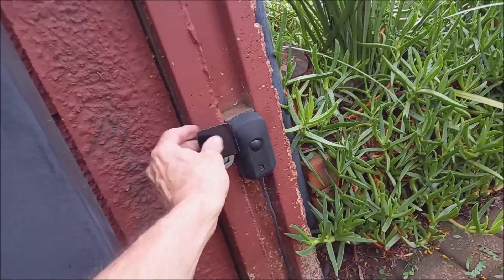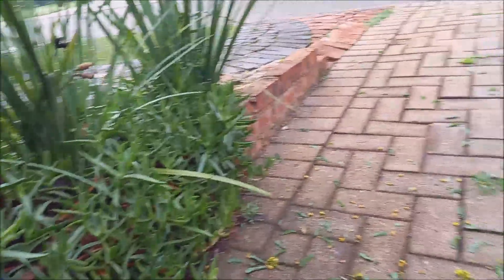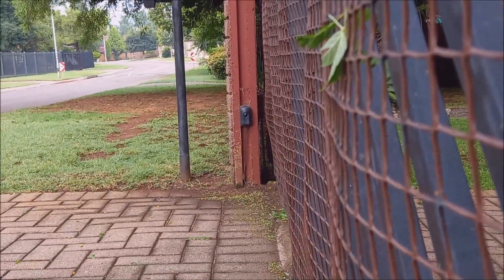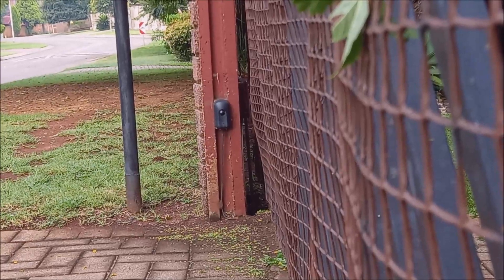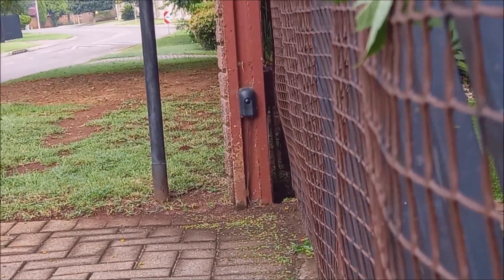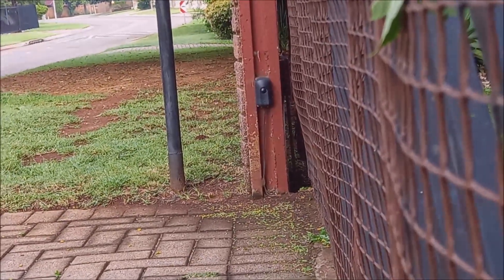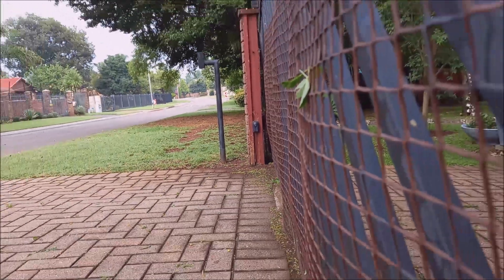This is where I put this lock on. But what happens if a car comes in with a trailer — the trailer can be higher than the sensor. The sensor goes underneath the trailer while it's going in or out, and then it doesn't trigger or stop your gate motor, and it hooks and damages your gate.